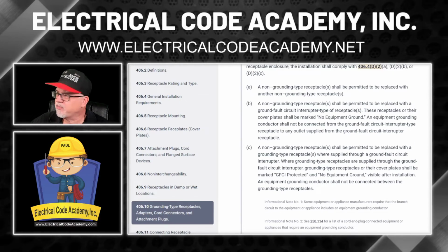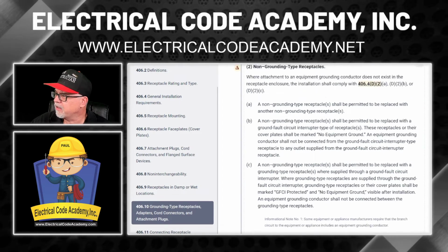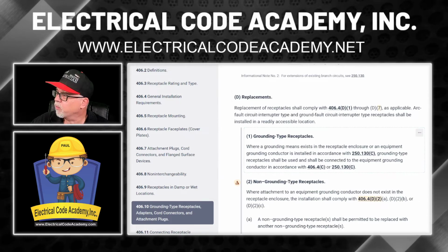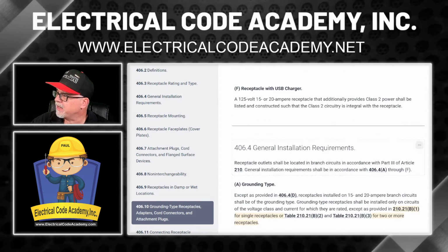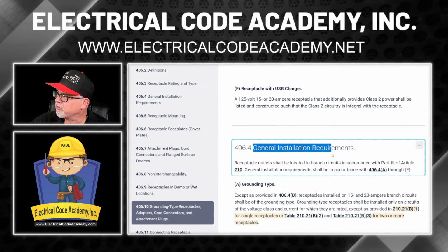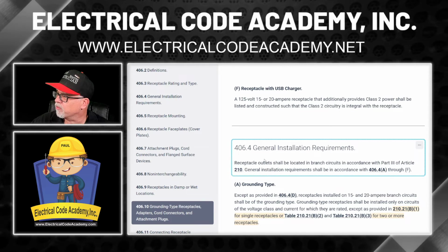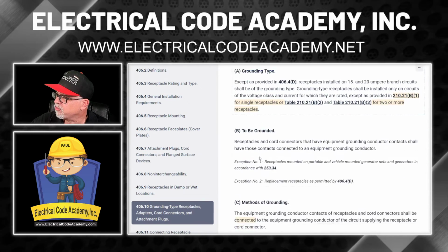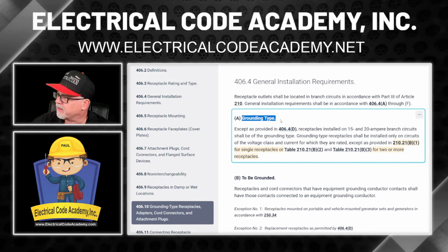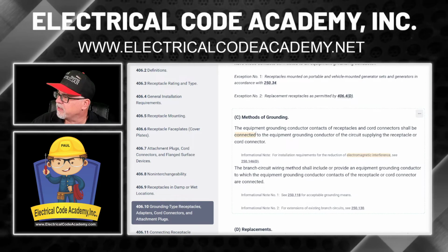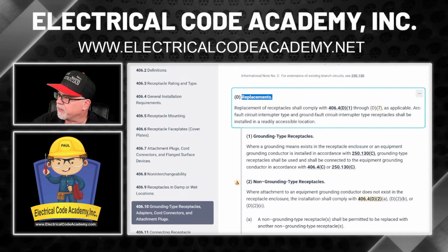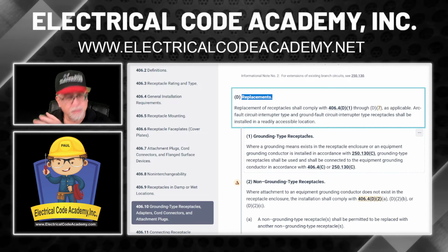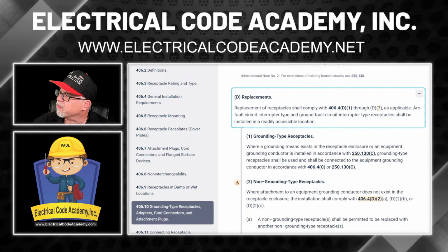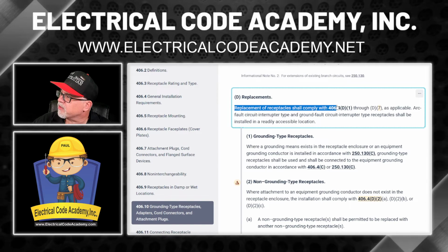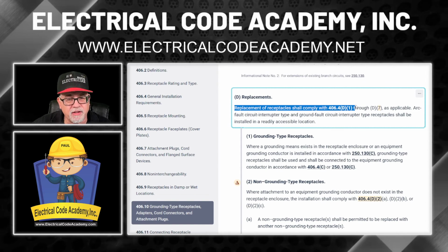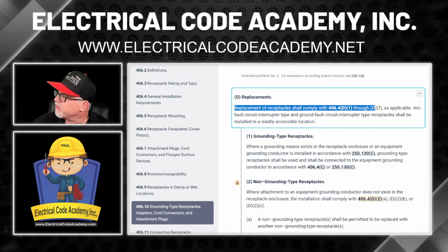So I'm at the NEC. I'm using Link. Link is a product from NFPA. And we're at the replacements. So here at the beginning of this is general installation requirements 406.4 for receptacles. And so again, obviously they have to be the grounded type. And it goes on and says, well, what about if you're doing a replacement? So if we're doing a replacement like what he's doing, it says replacement receptacles shall comply with 406.4 D1 through D7, so you have different options here, as applicable.